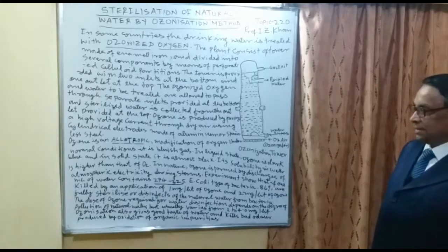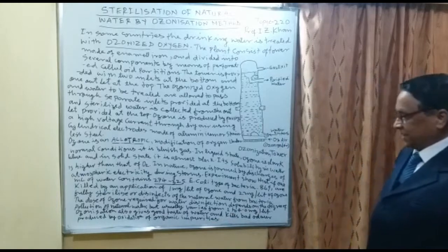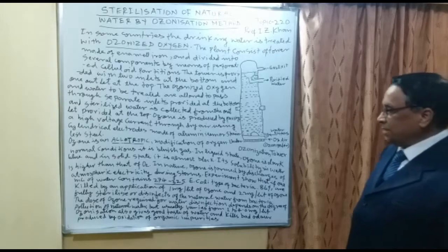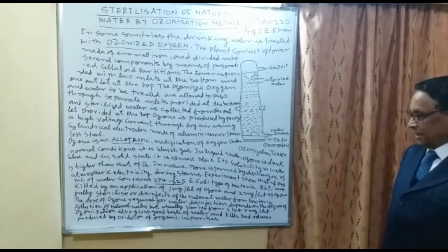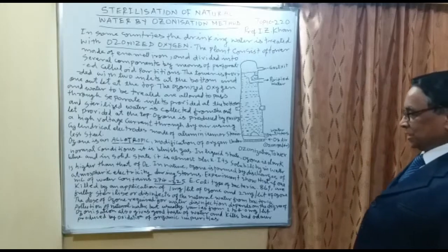86 percent of E. coli are killed by one milligram of ozone per liter. If we add two milligrams of ozone per one liter, the water will be fully sterilized and all bacteria will be killed. The dose of ozone required for water disinfection depends on the degree of pollution of natural water, but usually it varies from one to four milligrams per liter.